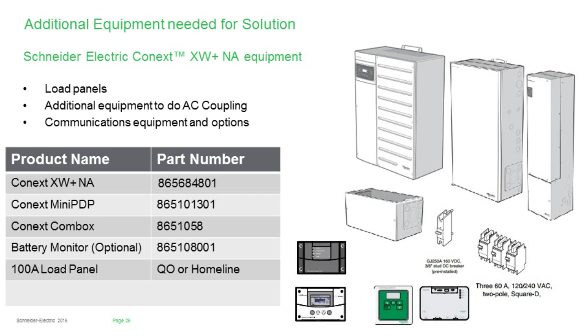And then finally, of course, we have our 100 amp load panel, which is where we're going to put our critical loads. If we are AC coupling, then that's where we're going to be bringing the output of our PV inverters and connecting it to that battery-based solution. So again, can't say it enough times, the output of the inverter, which is going to be the grid forming inverter, needs to be connected to the PV inverter so that the PV inverter has that qualified AC source for creating power and providing loads both inside the home as well as charging those batteries.